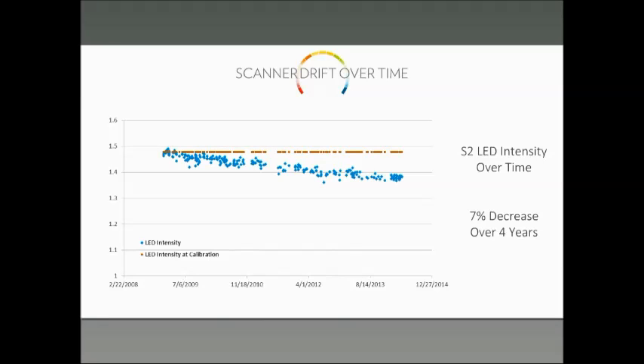There are internal calibrations and algorithms that help to correct for that. Our sense is it's not a large change and it's not going to be very significant to you. However, there is a sense over time, especially in the field, that maybe there is a downward drift. We're looking at that more closely, and certainly with the S3 we're going to pay more attention to that. We may actually put into place a recalibration every year or two to make sure that the devices are still accurate.